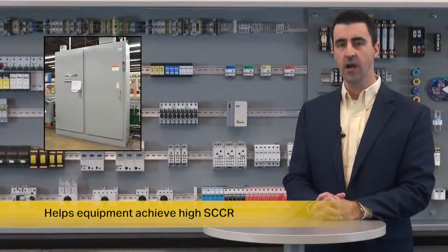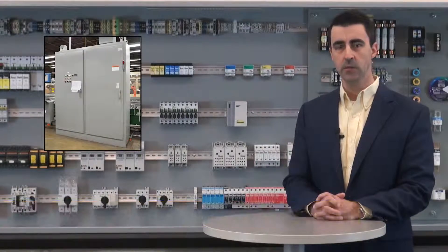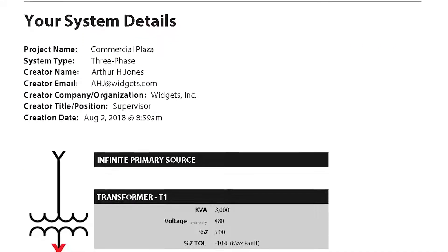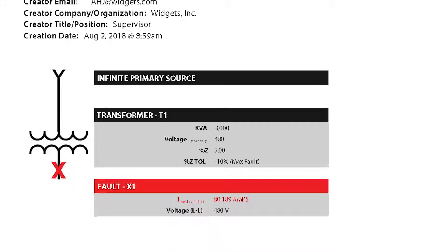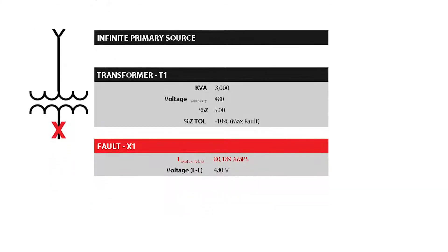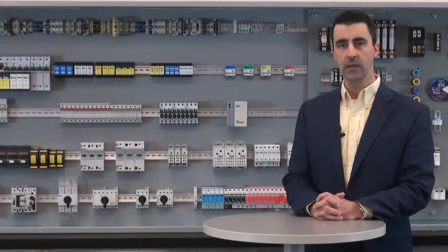Fuse current limitation helps equipment achieve high short circuit current ratings. Branch circuit components inside industrial control panels and machines, HVAC control panels, and other UL 508A listed equipment can be protected by current limiting fuses in the feeder circuit. The low peak let-through can help raise the overall equipment short circuit current rating.